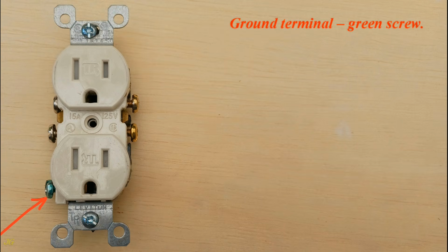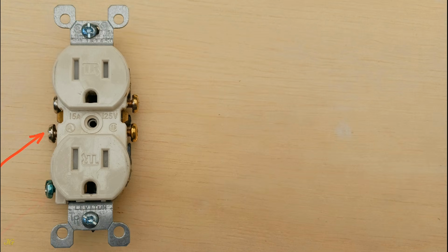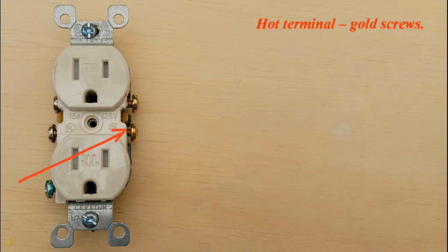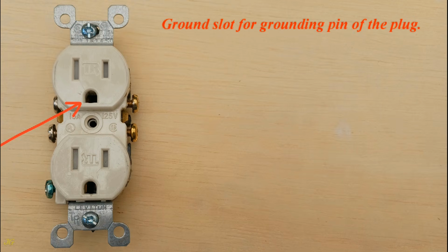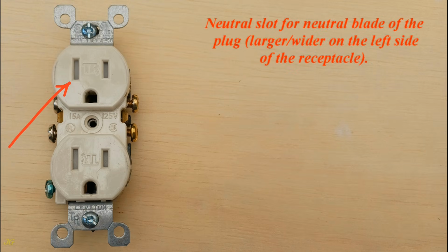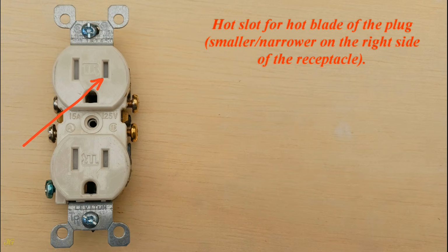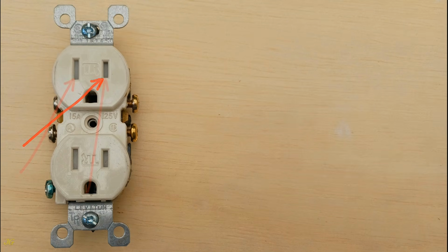Ground terminal, green screw. Neutral terminal, silver screws. Hot terminal, gold screws. Ground slot for the grounding pin of the plug. Neutral slot for the neutral blade of the plug, larger, wider, on the left side of the receptacle. Hot slot for the hot blade of the plug, smaller, narrower, on the right side of the receptacle.